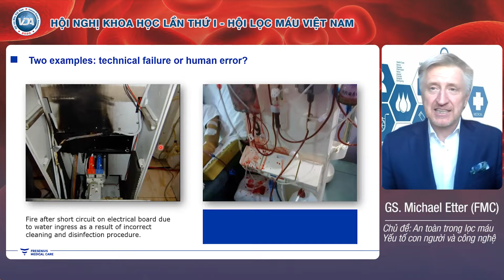If you look on the picture on the right-hand side, that's a typical blood spill because of a blood leak in the dialysis circuit. So here, the tube detached from the pump segment in the machine. This, you would say, is a technical problem. It's an issue that happened during the manufacturing of the bloodline. There was an error and the piece didn't hold. But one point I want to highlight here, this looks terrible, but we all know that a small amount of blood can create a lot of drama.